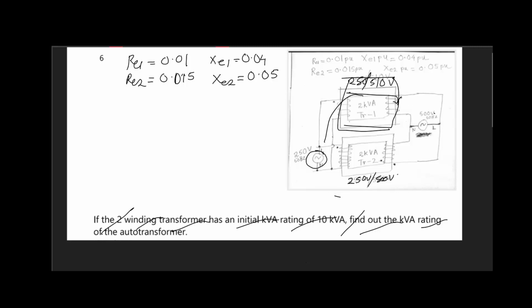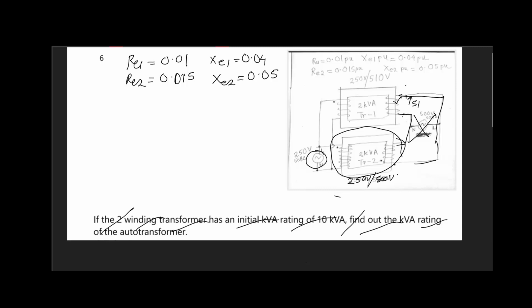So the first transformer voltage goes down and the second transformer voltage goes up, and eventually we reach a steady state condition, an amicable equilibrium, where neither the first one gives 510 nor the second one gives 500, but a voltage in between these two, and that voltage will be decided by the amount of circulating current and the rating of the transformers.